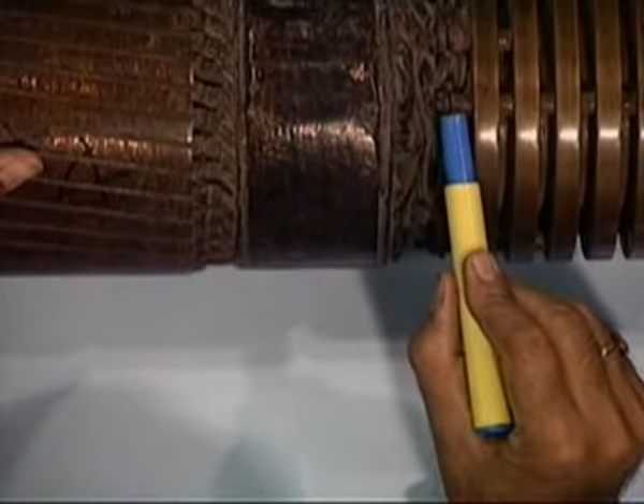So you will notice that each of the ends is connected to a particular slip ring. If you look at this terminal, it is connected to this slip ring through insulation. If you look at this terminal, it goes to this slip ring here. So maybe I'll turn it here. If you have this terminal, it goes to this slip ring. So each terminal goes to one particular slip ring. There are several slip rings, and then the brushes will touch the slip rings. Brushes are stationary, so you will have a separate brush arrangement like that. And at the brushes they are short circuited.